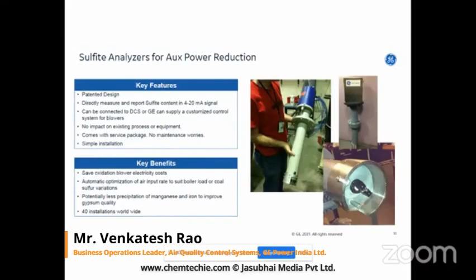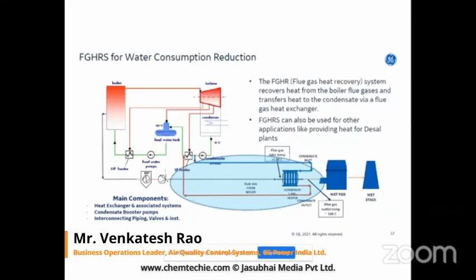We also have a solution, with almost 8 to 9 installations over the last few years, which we call a flue gas heat recovery system. Instead of a GGH, we go in for a zero leakage heat exchanger in order to reduce water consumption into the FGD. From around 130 to 140 degrees, we first bring down the temperature of the flue gas to 100, which helps reduce the water required to take the gases to saturation by almost 30 to 40%. This has worked well in 7 or 8 of our installations globally, and we would like to take this forward with NTPC and other power producers to reduce water consumption, which is one of the key problems the country is facing.